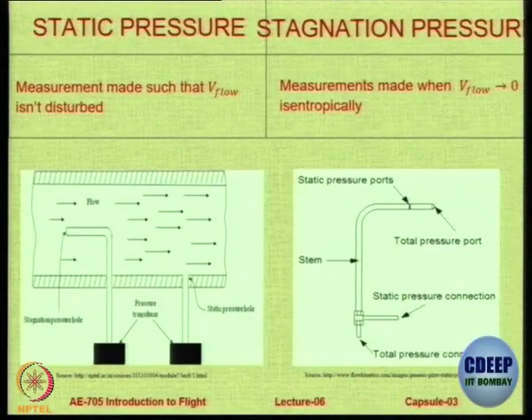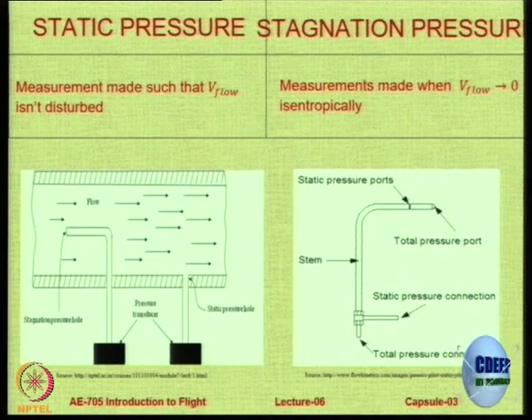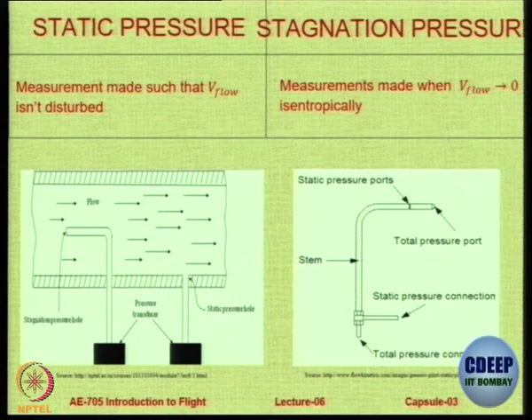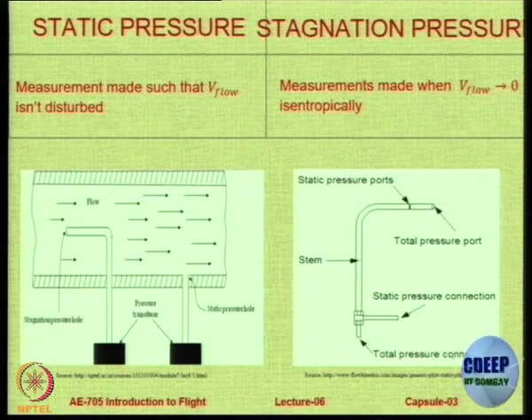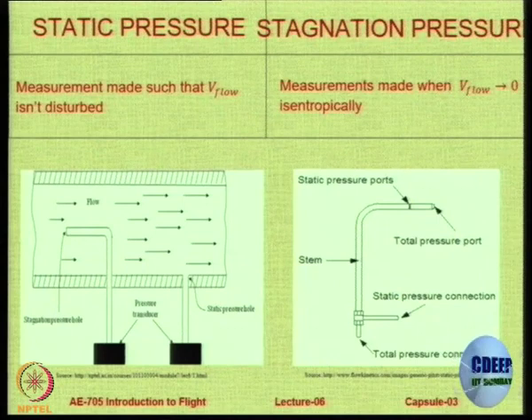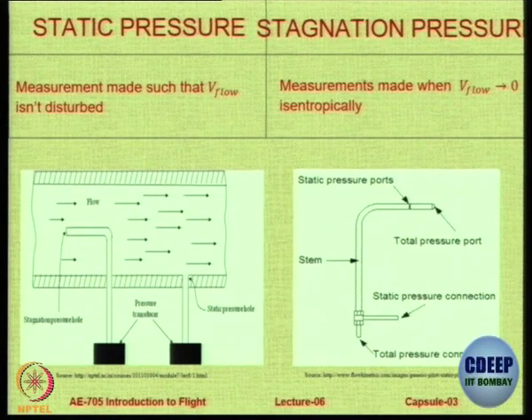In static pressure measurement there is a pipe or probe that is flush with the inner edge of the tube — not protruding inside — and the pressure it measures is called static pressure. On the left is a tube that probes inside, disturbing the flow, and that measures total pressure. On the right-hand side there is a similar arrangement: a total pressure connection and on the side a static pressure connection. The bent stem has static pressure ports on the sides and in the front a total pressure port that takes the incoming flow head-on.